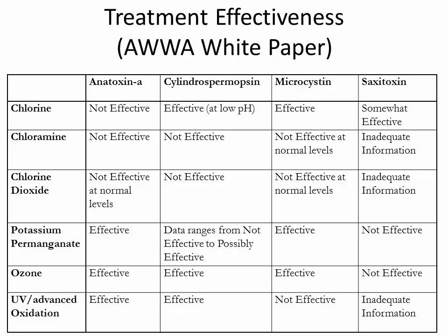So, in summary, treatment effectiveness, chlorines, show you across there, most effective with microcystin, not so effective with the alkaloid toxins. Chloramines, not much effect all the way across. Chlorine dioxide, not very good. Potassium permanganates, effective on anatoxin. In general, it's reasonably effective. Ozone, effective except for saxitoxins.